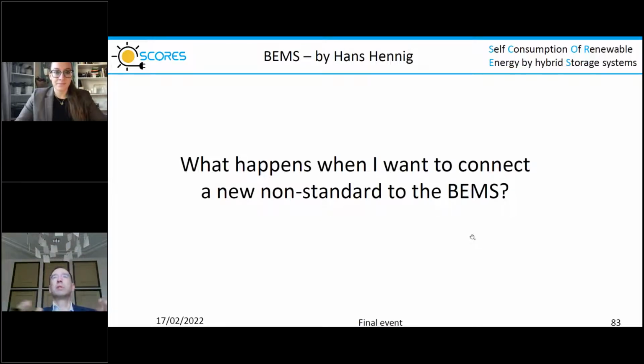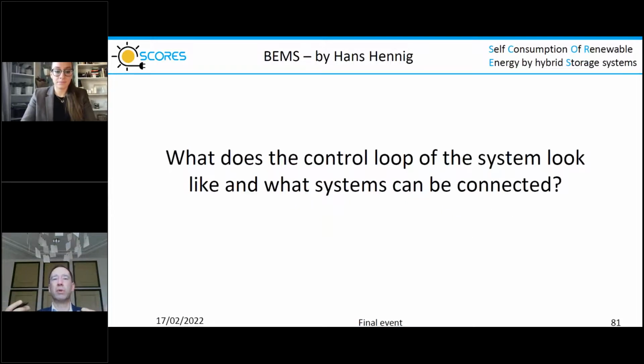What you have in practice is field equipment that communicates somehow with the BEMS, using either Modbus, BACnet, or some kind of protocol that the controllers can interface with. All the data enters the controller, which changes the local communication language to something it can understand. In our case, that's BACnet. It builds BACnet objects because they're fairly easy to work with. Those get transferred to the BEMS system, which makes sense of what's happening. Based on that, it devises a strategy, which is communicated back to the controller and to the field equipment. Once the field equipment acts, the controllers sense that something is happening, and feed that information back to the BEMS as a check.